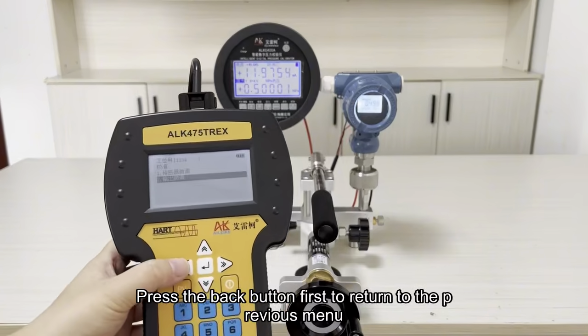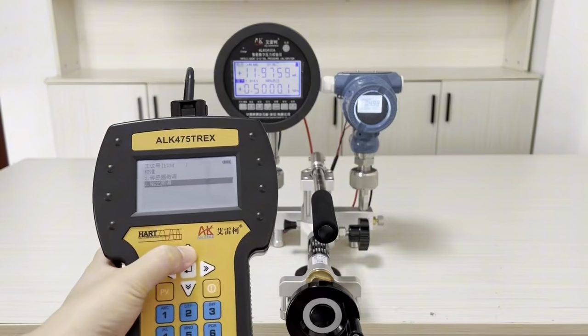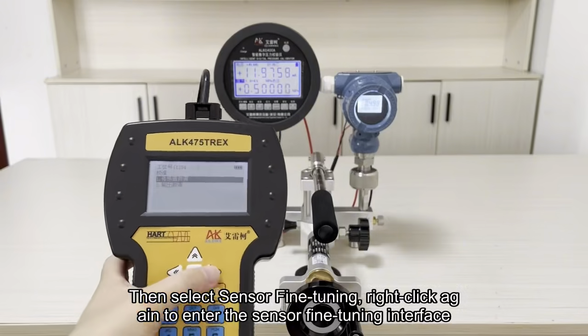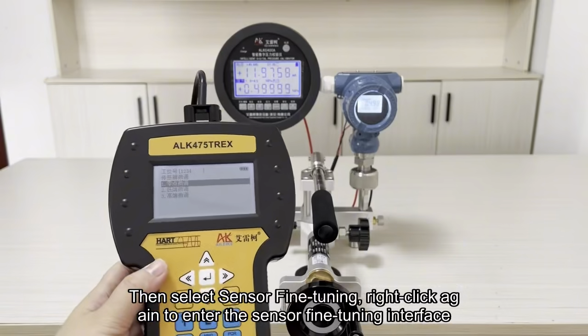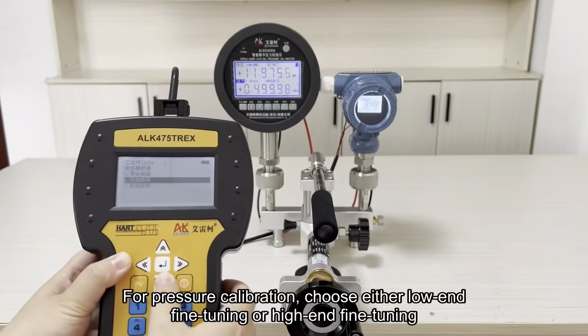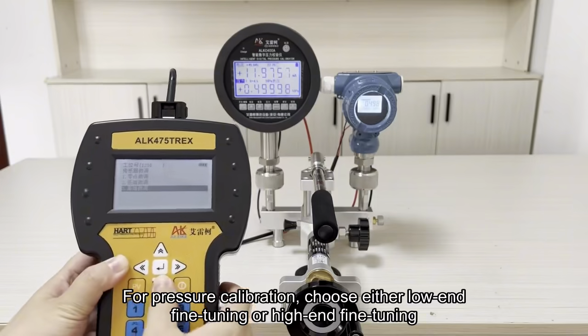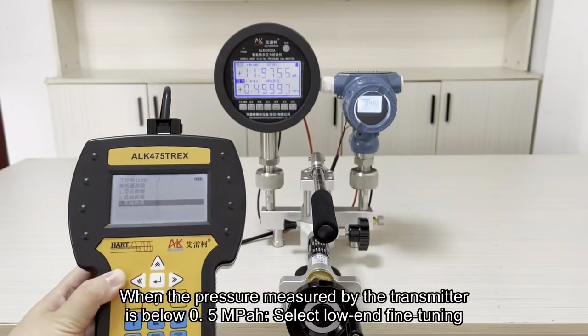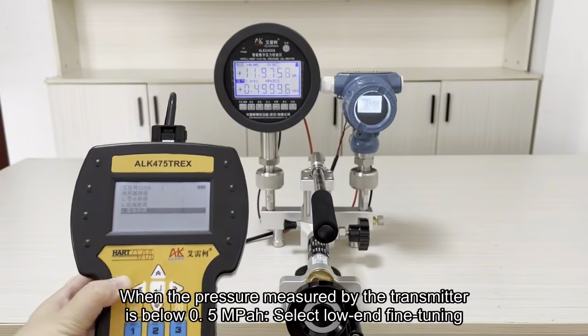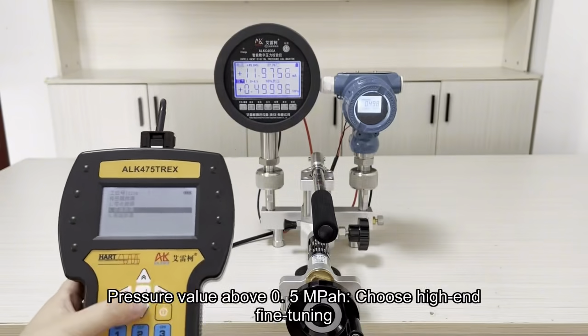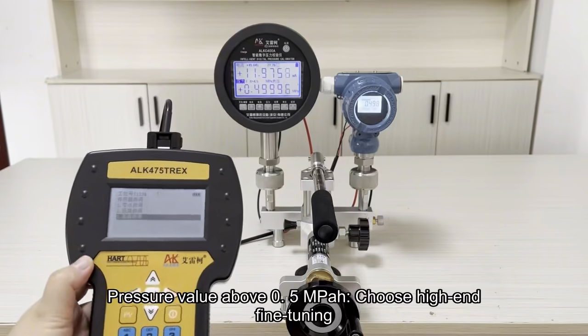Press the back button first to return to the previous menu. Then select Sensor Fine-Tuning. Right-click again to enter the Sensor Fine-Tuning interface. For pressure calibration, choose either low-end fine-tuning or high-end fine-tuning. When the pressure measured by the transmitter is below 0.5 MPa, select low-end fine-tuning. Pressure value above 0.5 MPa, choose high-end fine-tuning.